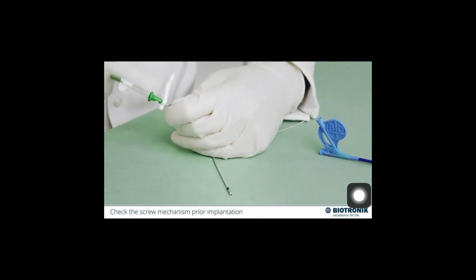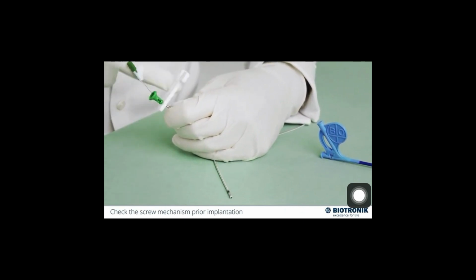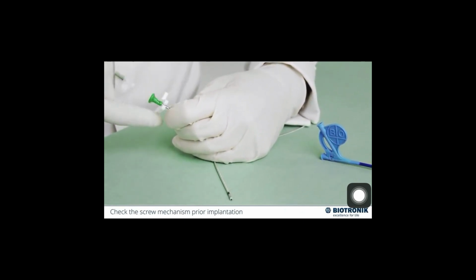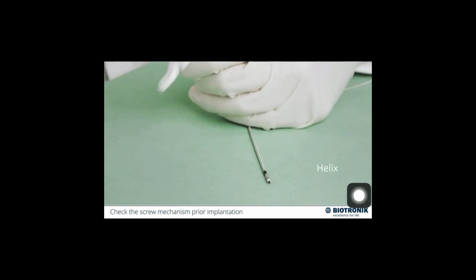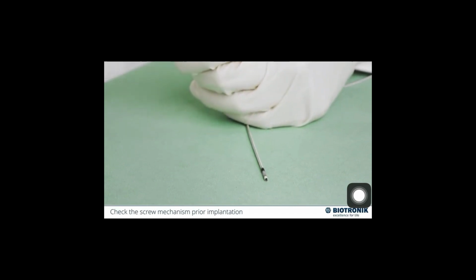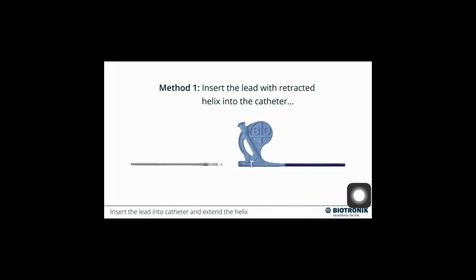First, we must check the screw mechanism by slowly extending and retracting the helix with the stylet fully inserted prior to the implantation. When locating the target area, the lead shall be inserted into the catheter and the helix exposed. In order to ensure that the helix is completely extended, it is necessary to complete one of two actions.